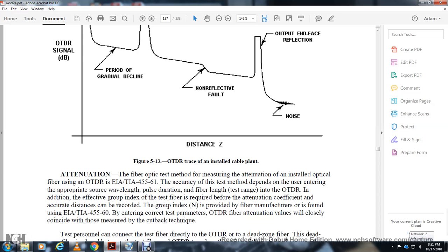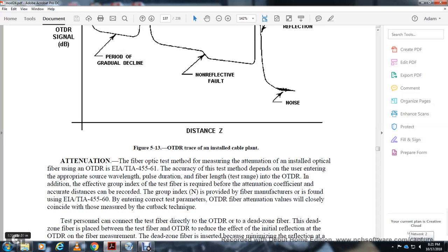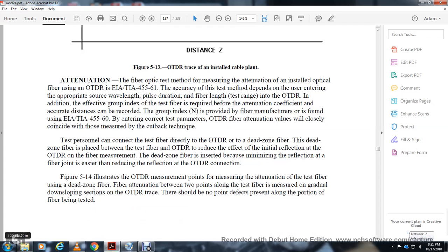Accurate OTDR measurements require entering the correct test parameters including the group index of refraction for the fiber, which must be provided by the fiber manufacturer per EIA/TIA-455-60. A dead zone fiber is inserted between the OTDR and the test fiber to reduce the effect of the initial Fresnel reflection. The dead zone fiber minimizes reflections at the OTDR-to-fiber joint interface. Figures 5-14 illustrate the OTDR measurement setup with the dead zone fiber and the method for measuring attenuation between two points along the test fiber.